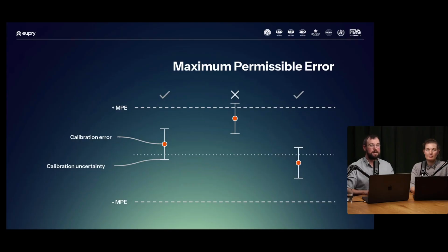Another thing, as I mentioned, is calibration uncertainty. While this might be a little bit confusing, the dot in the center of these whiskers is the calibration error, and the central dotted line is 0 degrees. So let's say the dot was at the center. We believe that it measures 0.0 degrees off. But we almost always have some calibration error. What the whiskers are is the calibration uncertainty. So how sure are we in this result?